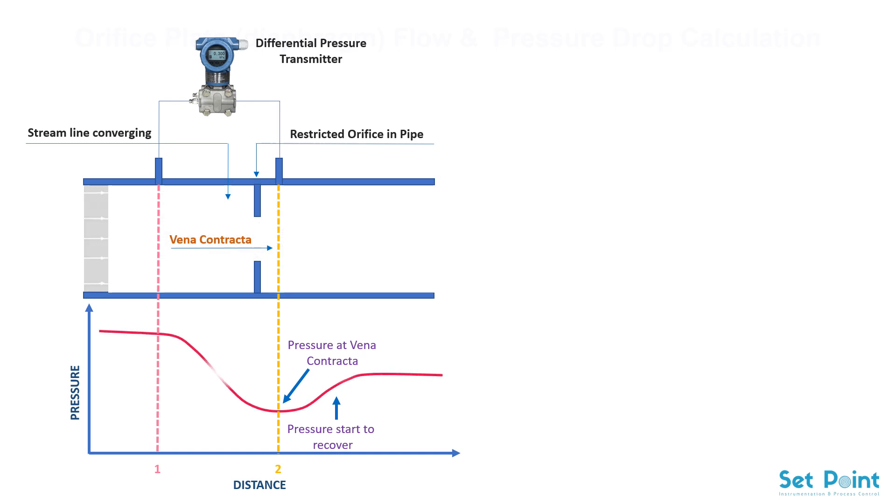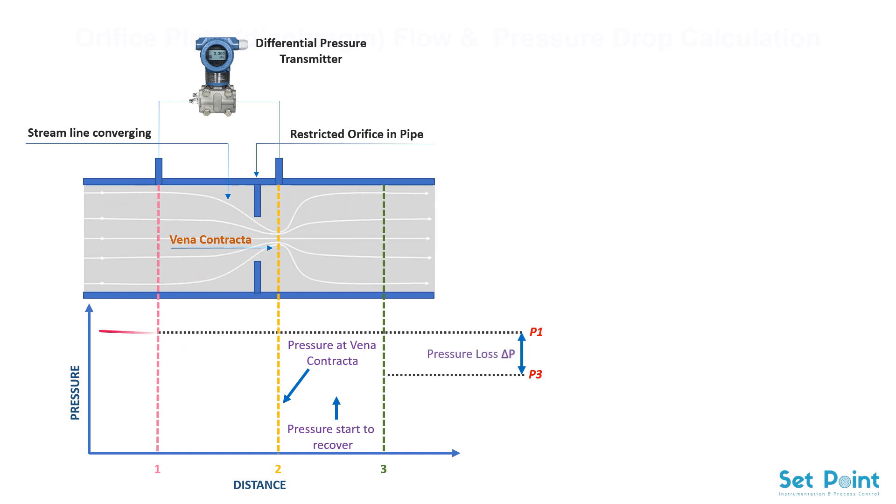The pressure at section 3 is always less than pressure at section 1. The pressure difference between sections 1 and 3 is non-recoverable and known as permanent pressure loss. Pressure difference between section 2 at vena contracta and section 3 is known as pressure recovery.